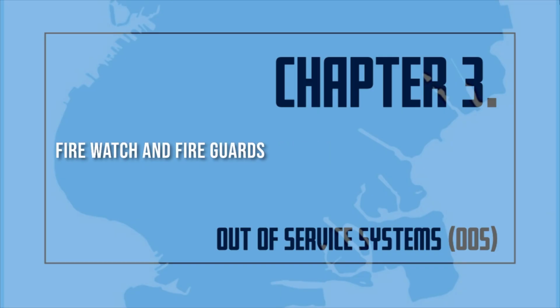Fire watch and fire guards. When a fire protection system is out of service, fire watch personnel must continuously patrol the area affected by the out-of-service fire protection system to which such person has been assigned, keeping constant watch for fires. Be provided with at least one approved means for notifying the fire department and emergency preparedness staff. Immediately report any fire to the fire department and notify the emergency preparedness staff on premises. Be trained in the use of portable fire extinguishers. Be responsible for extinguishing fires limited in size and spread that can be readily extinguished. Maintain a record of such fire watch on the premises during the fire watch and for a minimum of 48 hours after the fire watch has concluded.